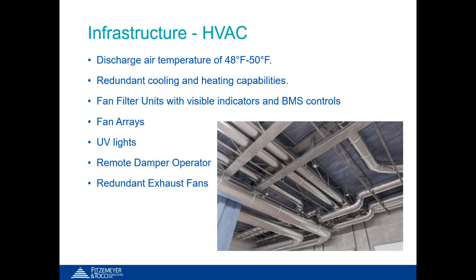To meet air temperature and humidity requirements, the AHU cooling coils must be sized to meet a discharge air temperature of 48 to 50 degrees Fahrenheit. Typically, chilled water systems cannot maintain this leaving air temperature. Therefore, direct expansion coils and condensing units are often seen for these types of air handlers. The DX coils are more than capable of meeting 48-degree discharge air temperature, if not lower. It's a good idea to have partial redundant cooling via multiple coils, or if DX coils are used, a minimum of 2 individual refrigerant circuits. This will allow for the unit to still provide some cooling to the space if one of the coils or refrigerant circuits were to fail.